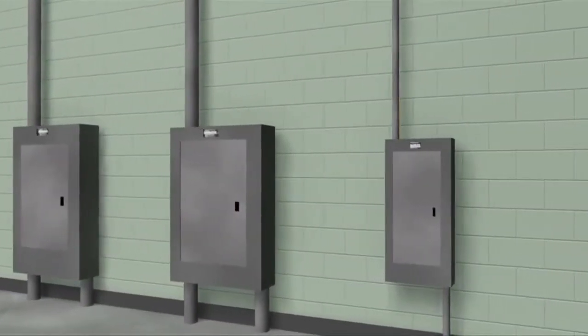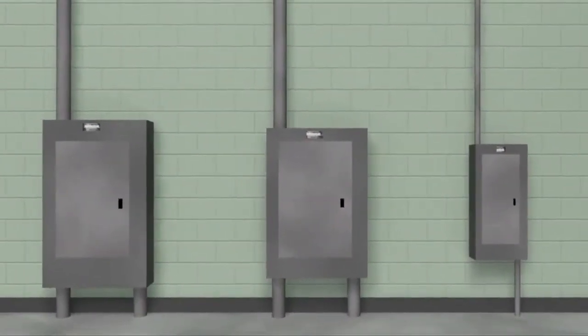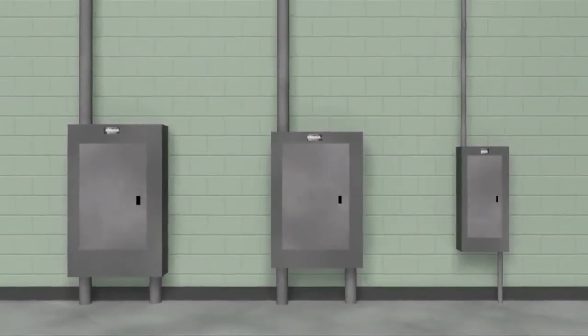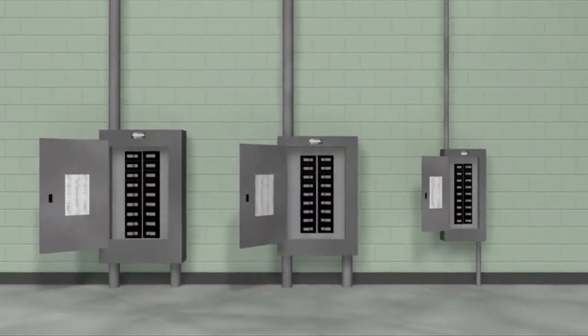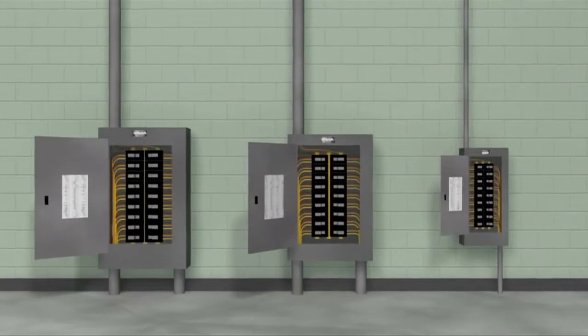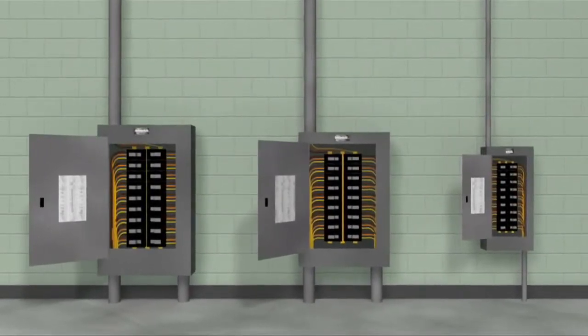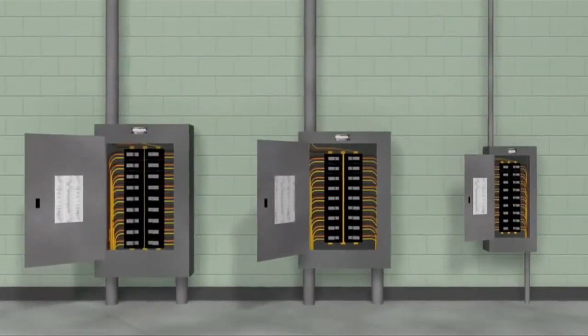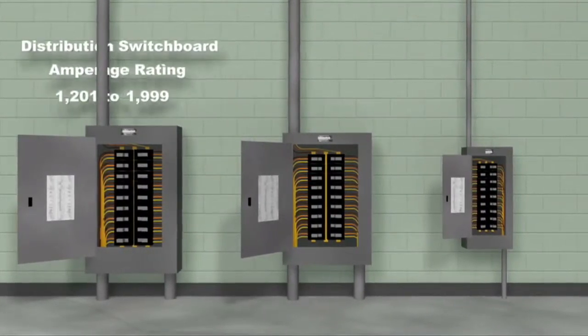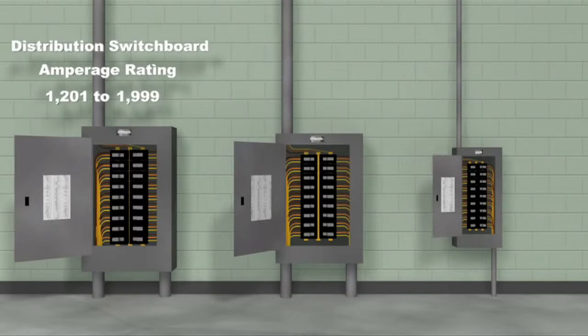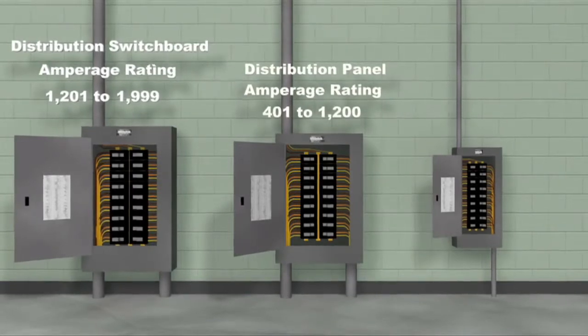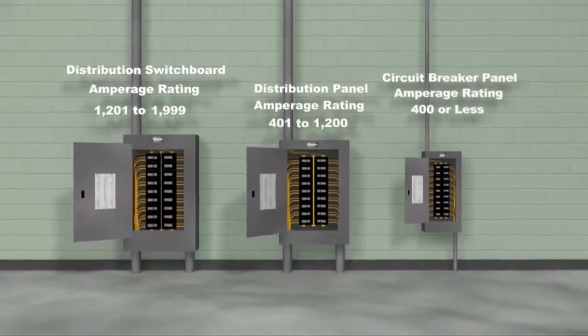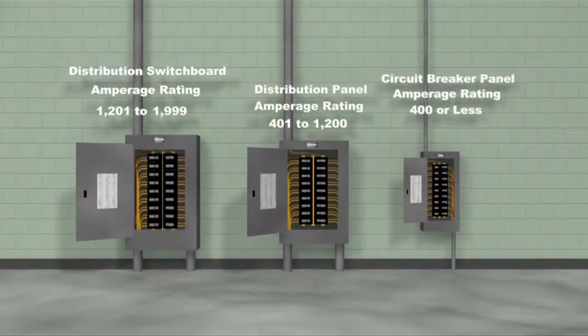A distribution switchboard, a distribution panel, and a branch circuit breaker panel all have the same functionality. They can contain many circuit breakers distributing voltage to all areas of the facility. What differentiates them from each other is their amperage rating. Distribution switchboard is an electrical panel with an amp rating between 1,201 and 1,999. A distribution panel has an amperage rating of 401 to 1,200. A branch circuit breaker panel has an amperage rating that is equal to or less than 400 amps.